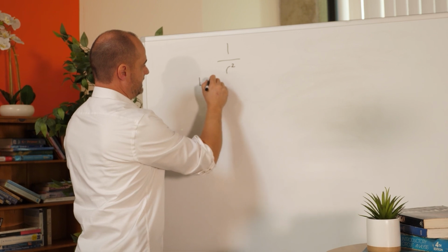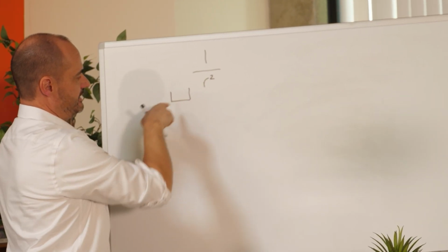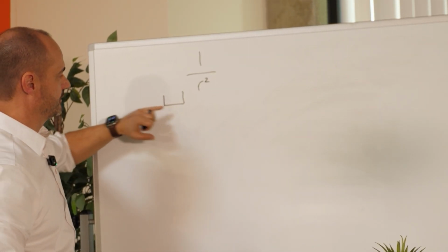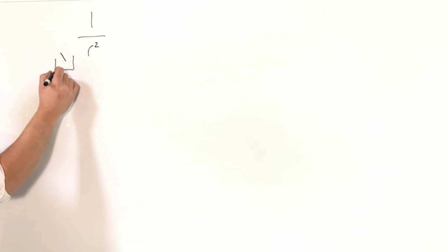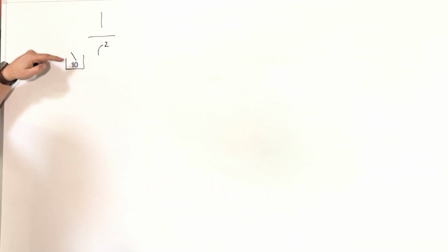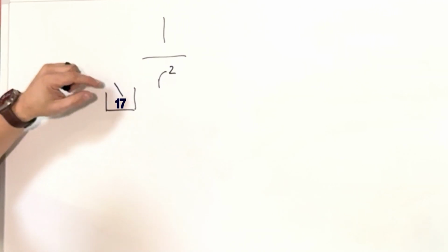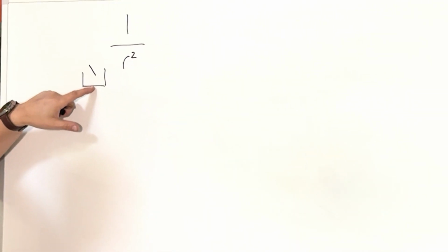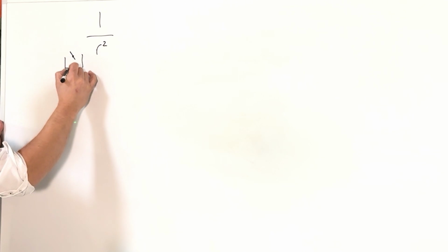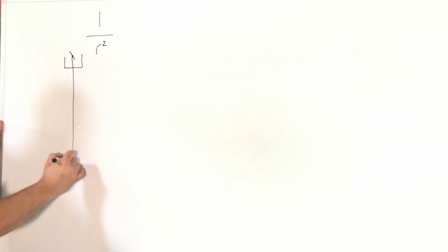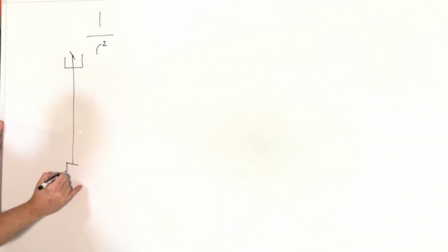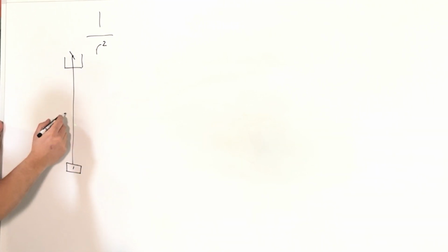This is the X-ray source, and what you see on a reflective source is the window, right? The target is somewhere inside the window, maybe 10, 11, 13, 17 millimeters inside. In a transmissive source, on an open source, the target is going to be right there at the window, so take that into consideration when doing this math. So here's the target, and the X-rays are hitting the component we're imaging, let's say component 1, and let's say this distance here is 3 inches.